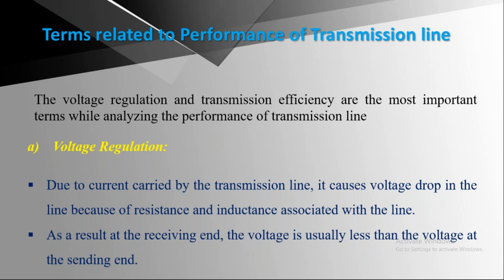Now, what are the factors affecting voltage regulation: generally in our transmission system, whatever voltage we are sending on the sending end, the complete voltage we are not getting at the receiving end. So there is some drop here. In loaded condition, Vs is not equal to Vr, that is sending voltage is not equal to receiving end voltage, because current flowing in the transmission line causes voltage drop due to the resistance and inductance associated with the line.